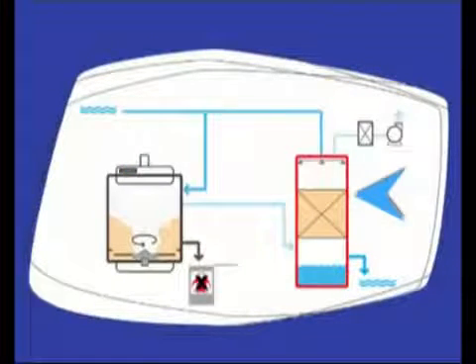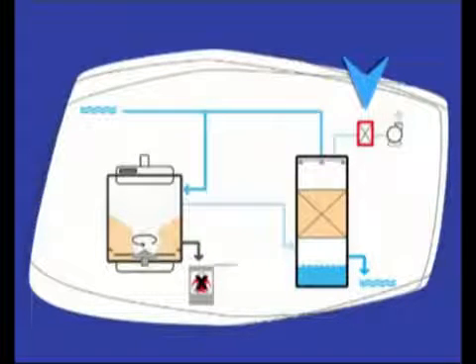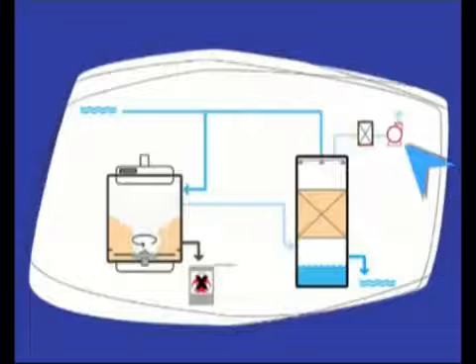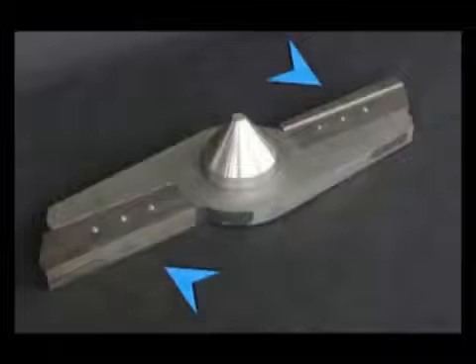A scrubber cleans up smoke, capturing any particles in suspension. A pump maintains the system under constant negative pressure to prevent any infected air from escaping into the environment. A filtration system treats outgoing air with an efficacy of 99.999%.